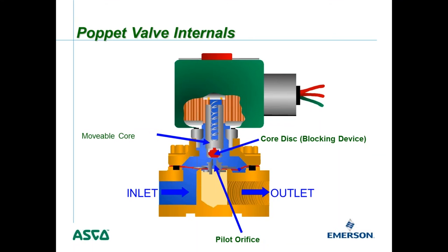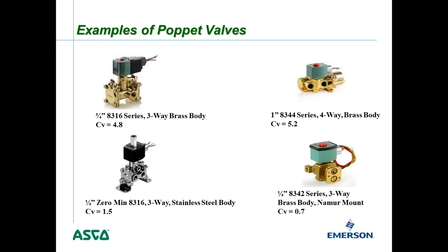There are many different types of poppet valves, but they all operate on the same principle with a pilot orifice and a bleed orifice that controls inlet pressure when the valve is closed. Examples include a three-quarter inch 8316 three-way valve with a brass body and CV of 4.8, a quarter-inch Zero-Min 8316 with a CV of 1.5, a one-inch 8344 four-way valve with a CV of 5.2, and a quarter-inch 8342 three-way Namur mount with a CV of 0.7.